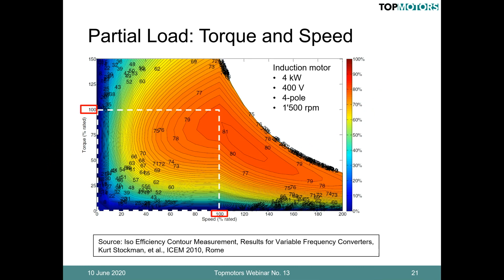But what the graph shows, when you test in a much larger band, you go up to 150% of the torque and you go up to 200% of the speed. You really try to use the power the machine has. You actually note that the maximum of efficiency is somewhere here. There is an efficiency peak island, 81%, that is around, I would say, 75% of the torque and about 80% of the speed, and it goes way to the right, and hits about 130% of the speed and about 50% of the torque.